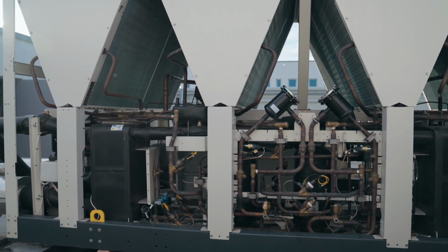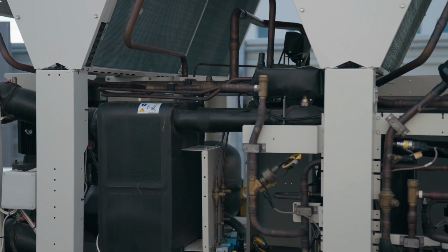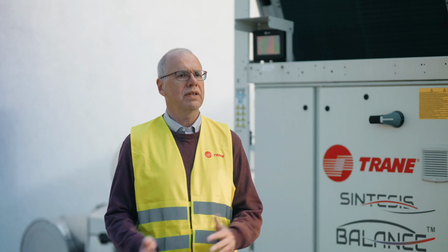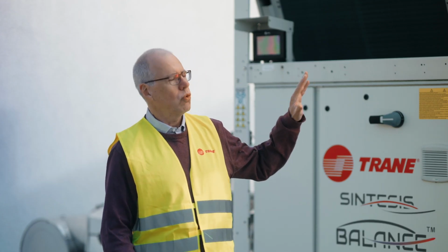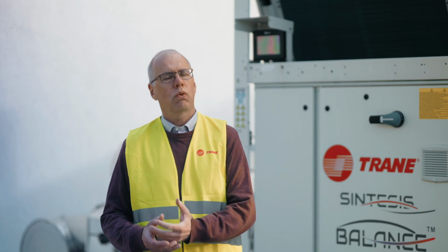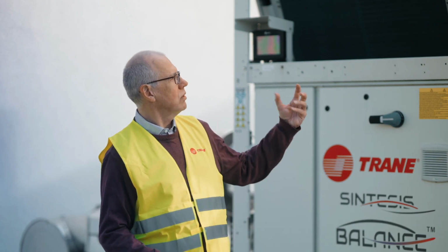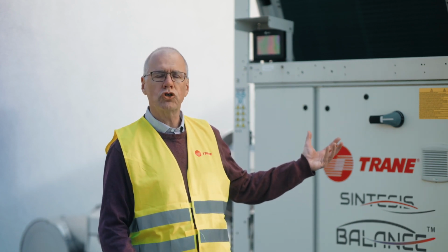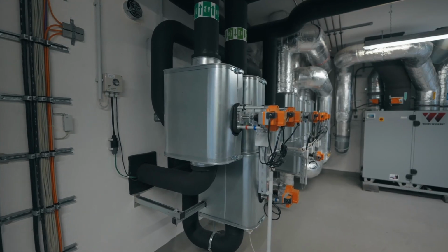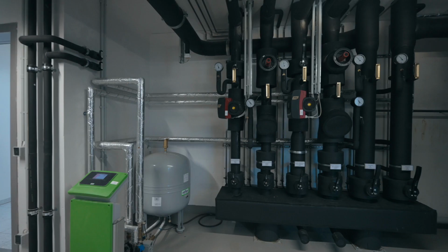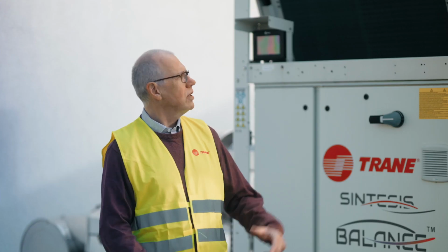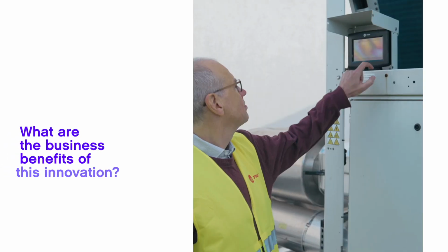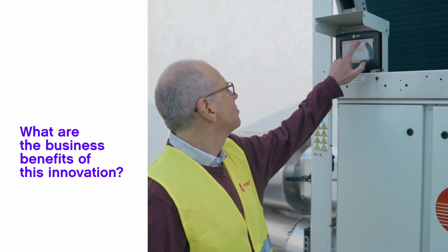This air heat exchanger is used to balance the difference between the heating demand and the cooling demand in the building. With the air heat exchanger, we can satisfy, I would say, what is missing in the building. Meaning when we have too much cooling demand, we can reject the excess heat. When there is not enough heating that can be recovered from the cooling side, we can extract it from the air.